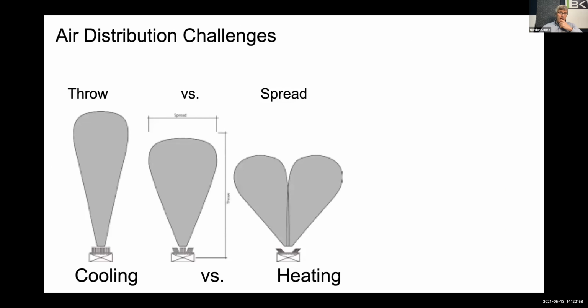And the next issue is the design of the grill. There are 2 different terminologies or technologies. You want a grill to either throw the air or spread the air. When we were in heating mode, in that room on the second floor, we're trying to bathe the walls. We like spread. Spread is done for heating. In cooling on that second floor, we want the air to get up past our head level. So we actually want to throw the air. Interestingly enough, most of the residential grill folks don't have any information on this. You actually have to go to a commercial-style grill to get throw and spread information. But I'm going to encourage you to give this some thought.